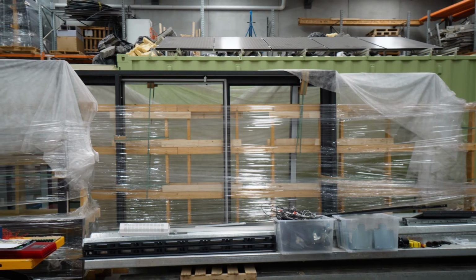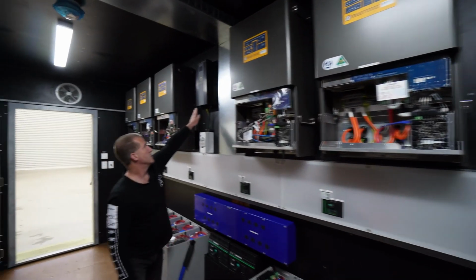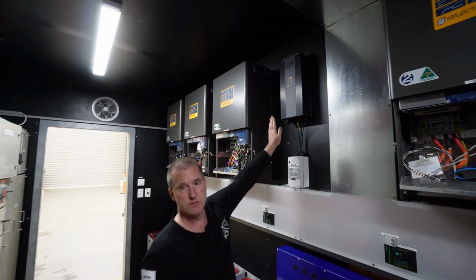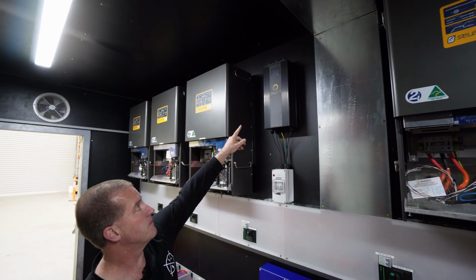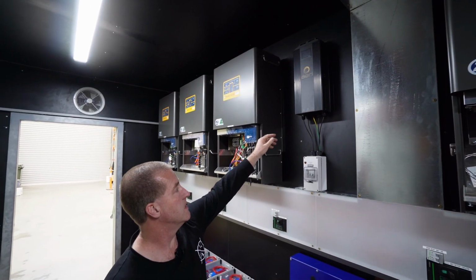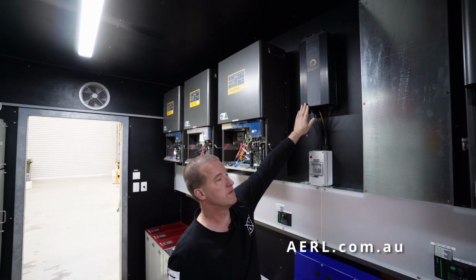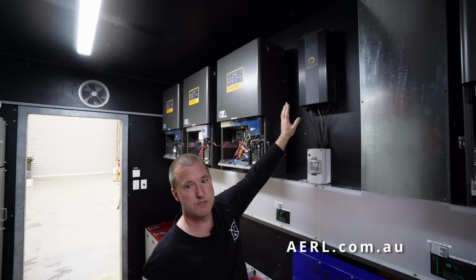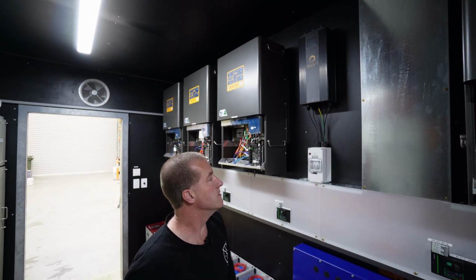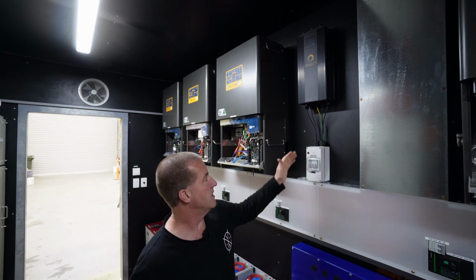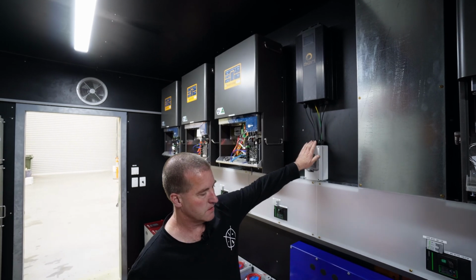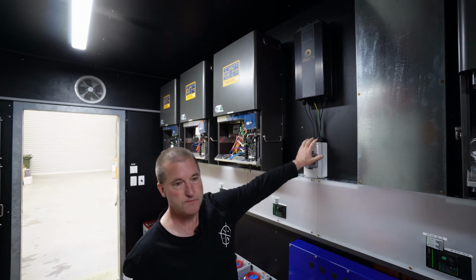You've got some solar PV on the roof—5 panels which come through a charge controller here that keeps it alive, so it can always recover using solar power. This is AERL, based in Queensland, and this is a little 30 amp regulator that converts 100 up to 300 volts DC into 138 volts that we can charge the batteries directly from the solar.